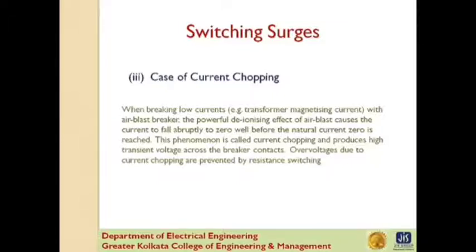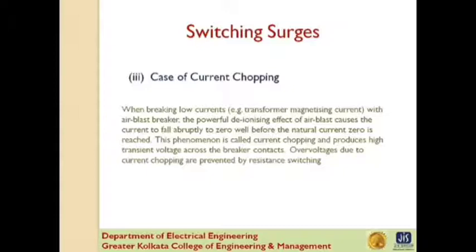Third case: current chopping results in the production of high voltage transients across the contacts of air blast circuit breakers. Unlike oil circuit breakers, air circuit breakers retain the same extinguishing power irrespective of the magnitude of current. When breaking low current, for example transformer magnetizing current, the powerful deionizing effect of air blast causes the current to fall abruptly to zero well before the natural current zero is reached. This phenomenon is called current chopping and produces high transient voltage over the breaker contacts. Overvoltages due to current chopping are prevented by resistance switching.